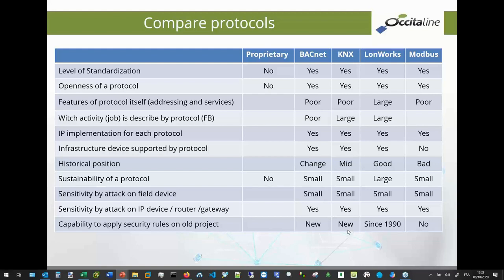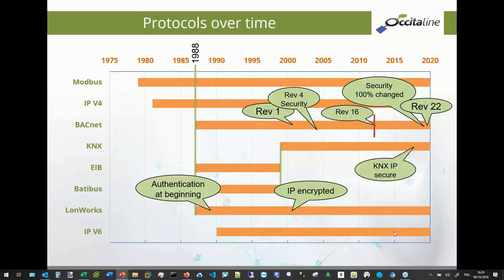An example, in BACnet, they removed one year ago, in November 2019, the chapter for security, and they replaced it with an annex, and the annex was proposed last year. Very, very critical, because if somebody implemented the security many years ago, since it was proposed in 2004, it's incompatible with the new version of BACnet. And KNX implemented the security a couple of years ago, and it's very, very new. And in Modbus, there is no protection, no security.